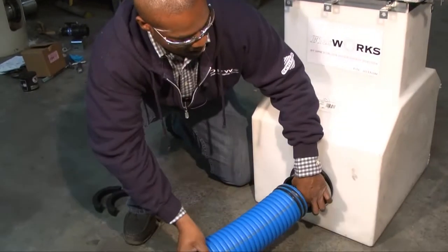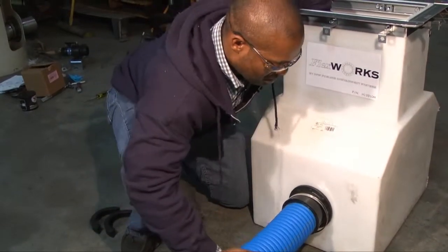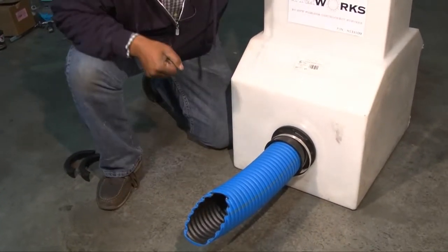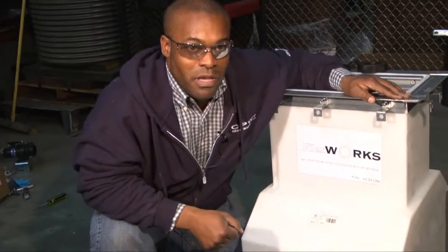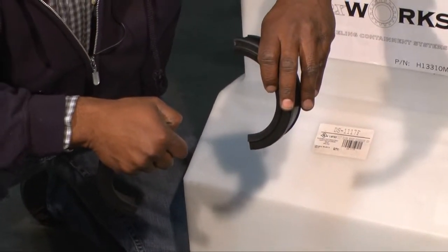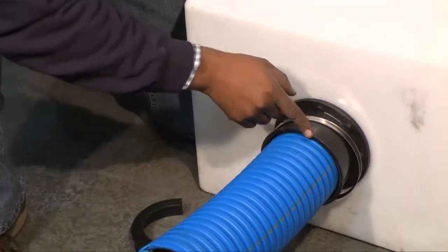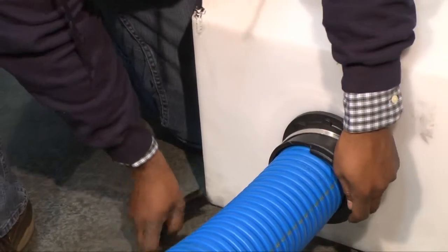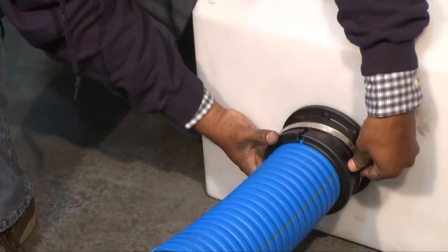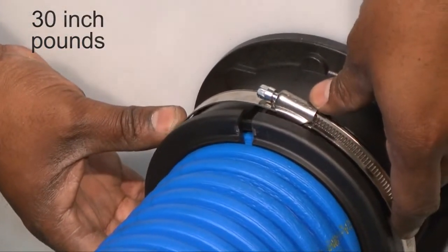Slide the access pipe near the front wall and work the seal into the outside body, paying special attention to proper seating. If you press the access pipe too far, you may encounter difficulty seating the seal properly. If you run into difficulty installing the seal pipe, move back the access pipe to allow for correct alignment and a new installation of the seal pipe. Once the seal pipe is installed, place the cap over the seal pipe and tighten the arrangement.